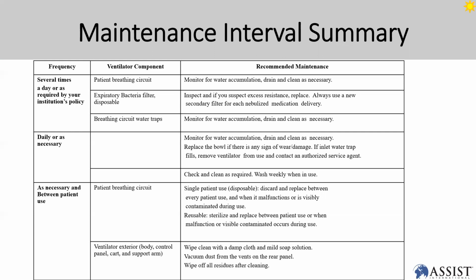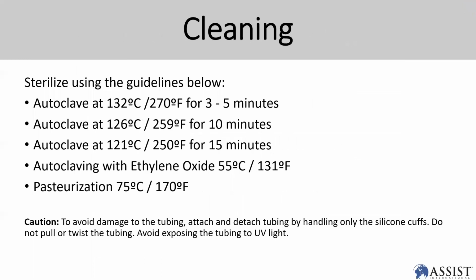So this is a daily routine that you have to do. Inspect the bacteria filter. The bacteria filter needs to be disposed of. Breathing circuit and water trap, some of it is disposed of, some needs to be cleaned and used again. So for the patient breathing circuit, it depends. Some can be single use, some are multiple use and need to be autoclaved. All these need to be carefully checked. When you talk about cleaning your breathing circuit, these are the steps you're going to use for the autoclave, the temperature and the time. Remember, most of the time when you want to autoclave your breathing circuit, clean it before you autoclave it.